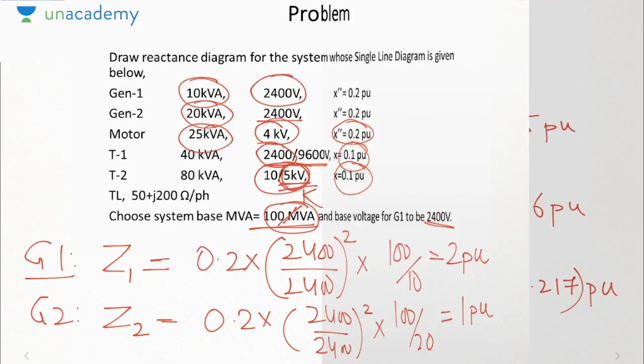Given for the motor is 25 kVA, assumed is 100, so change it to kVA, that is 100 kVA. New is 100, old is 25. So how much will this come out to be? It will be 0.2 into 4000 square divided by 4800 square into 4. So it will be 0.55 pu.